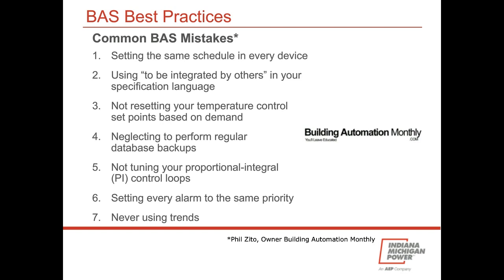Another one is not resetting your temperature control set points based on demand. If you don't reset the discharge air temperature when most of the VAV boxes aren't calling for cooling, this can often cause some of the boxes to kick into heating mode in the middle of July, for instance.